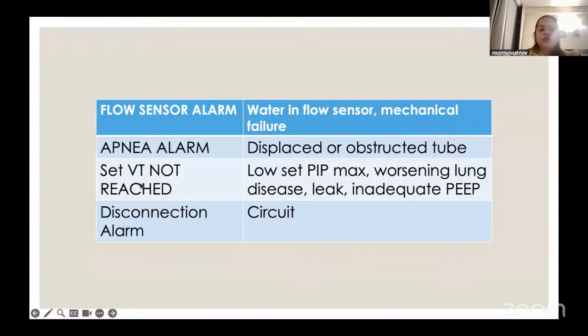Thirdly, the set VT not reached, and it is again a very common alarm which we go on muting. It's important to know that the VT is being determined by the PIP max that we are setting. In a case when we are using the VT mode, the baby decides how much pressure the baby needs to reach the set tidal volume. In a case where we are setting the maximum PIP low, the maximum PIP would be delivered and still the baby may not reach the set VT. So we should always keep the set PIP max around 20 to 22, so that if there is a worsening of the lung disease, the baby can determine how much PIP they have to take.